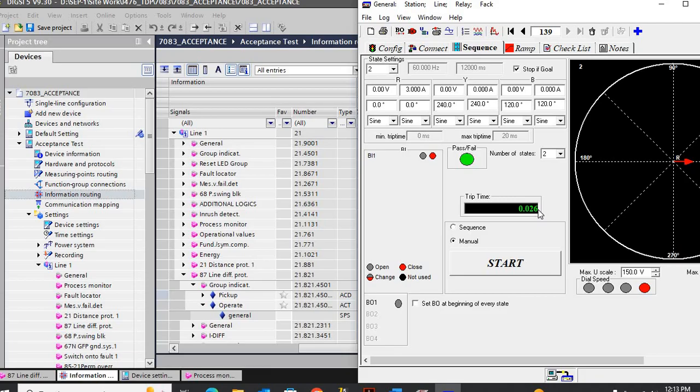If the same current is still available and is more than the switch-on-to-fault current, it's a heavy fault — it will consider it instantaneously. The differential will trip, and it will trip in instantaneous time.